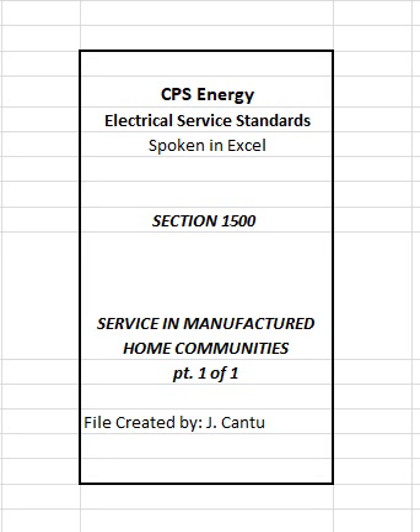2. CPS Energy will furnish and install the service lateral from the transformer terminals or secondary enclosure directly into a metering pedestal that is furnished and installed by the customer. Refer to Section 1800 and Figure 1501. 3. Surface-type meter mounting pedestals furnished and installed by customer. Customer's weatherproof service equipment and power outlet may be mounted on the pedestal.